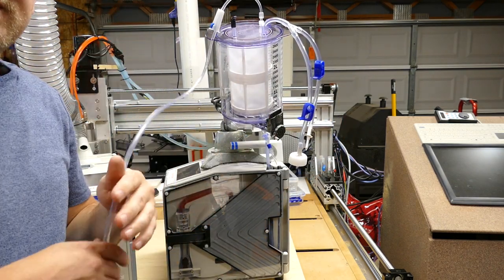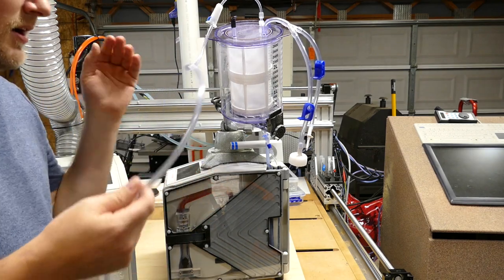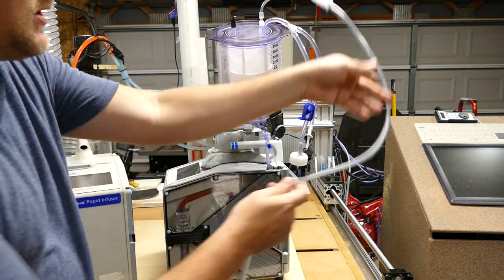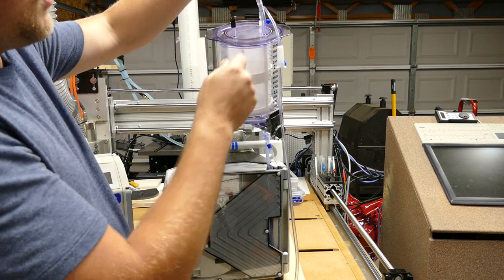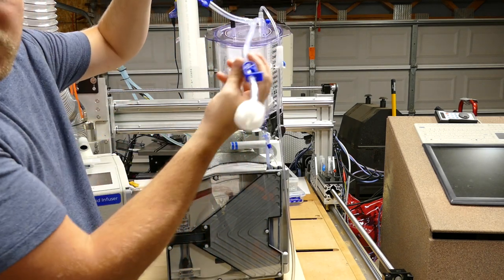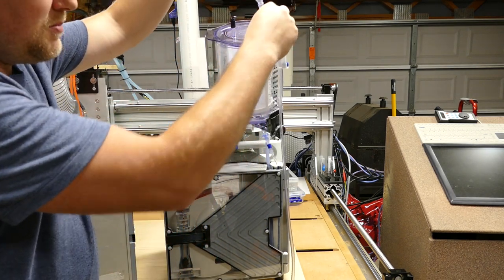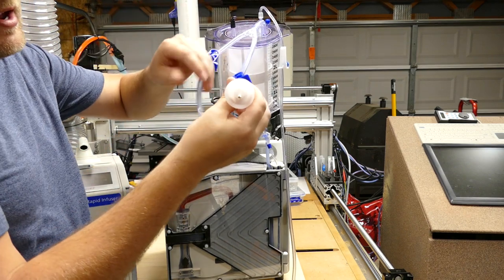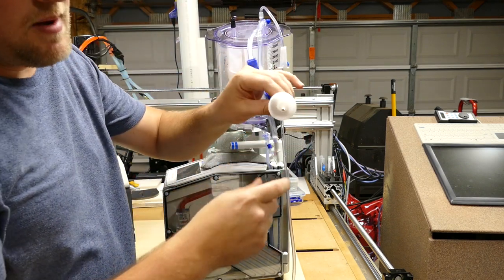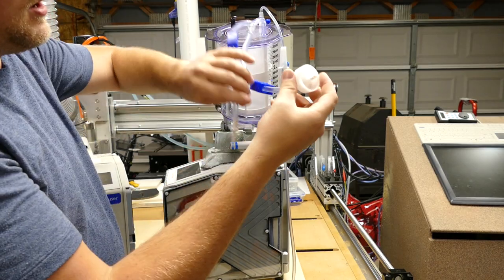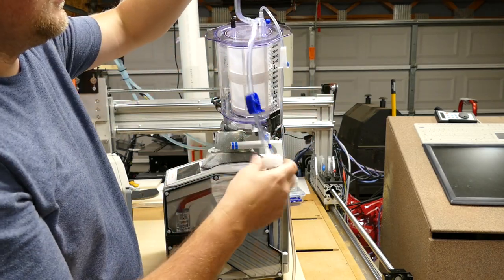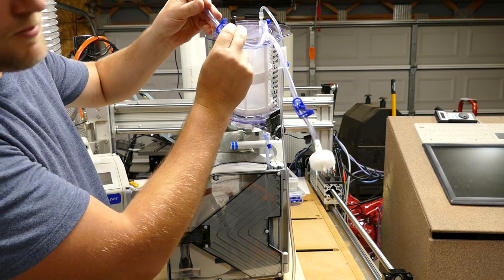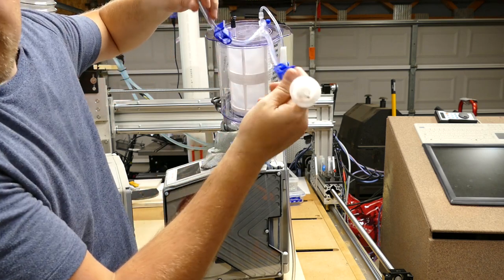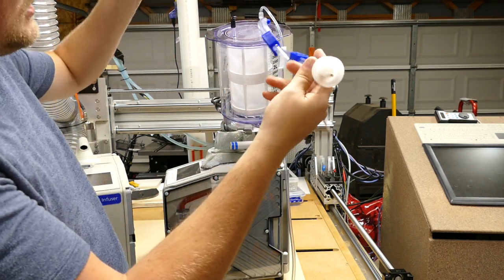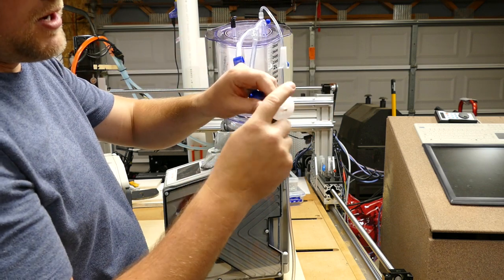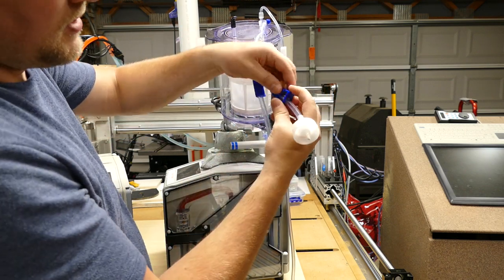Now, mind you, this is not how you set it up to run on a patient. This is how we're going to set it up to test the unit. Here, I've got one of the tubing Y pieces that comes with your sterile set. I have it pressed onto one of the fittings, and you can see here, I've got it stabbed into one of my bottle toppers, and this is going to be for my saline. The other line I've just got clamped off, and I might open that up if I need a little bit of ventilation while I'm filling. But other than that, all I'm going to use is this line right here. So I'm going to go ahead and unclip it.